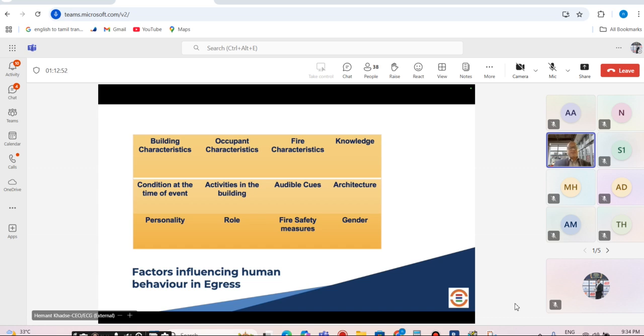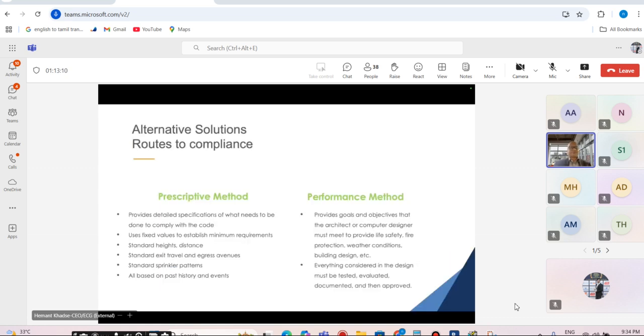So these are various factors that also influence the egress, and it is not addressed explicitly by any of the codes and standards. But as an engineer, you also have to look at them when you design the systems. It could be fire alarm as the life safety system, or connected auxiliary systems. So prescriptive and performance-based are always options available. It is not necessary that you restrict yourself only to prescriptive unless it is strictly enforced. But if there are site challenges because of the operation or the availability of existing structure, you can always look at the performance-based standard to meet your life safety objectives.